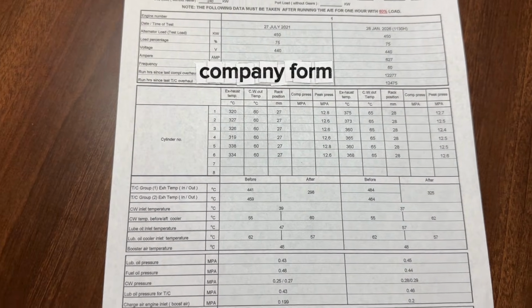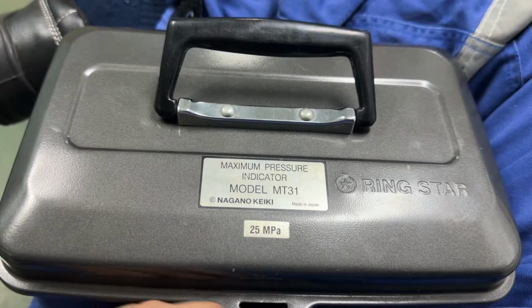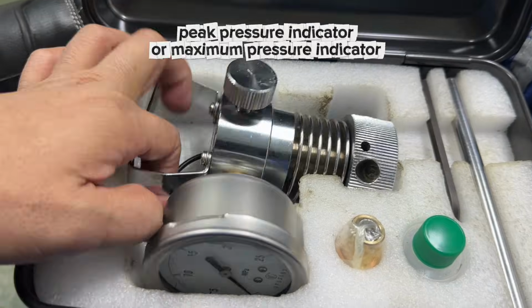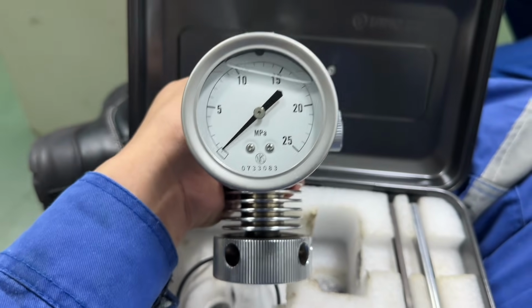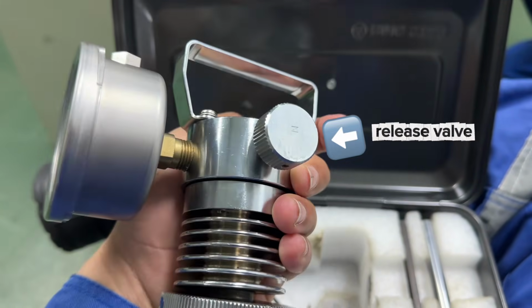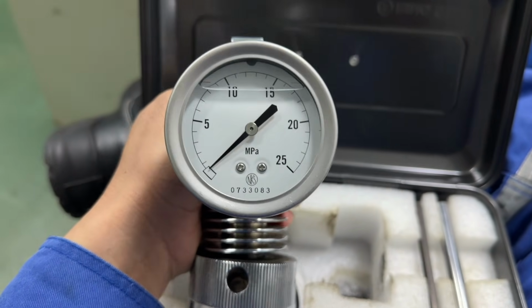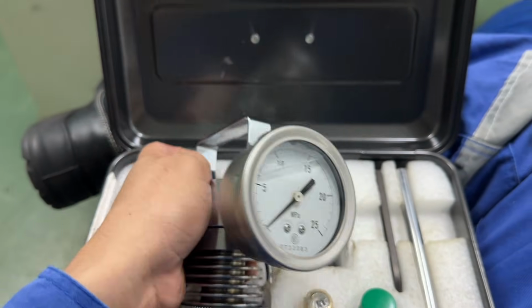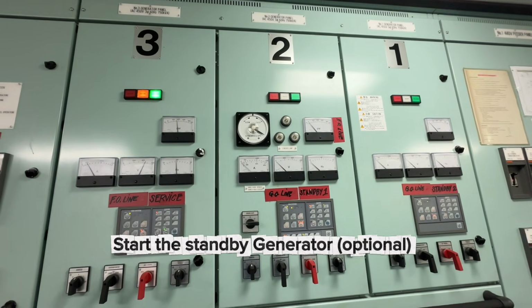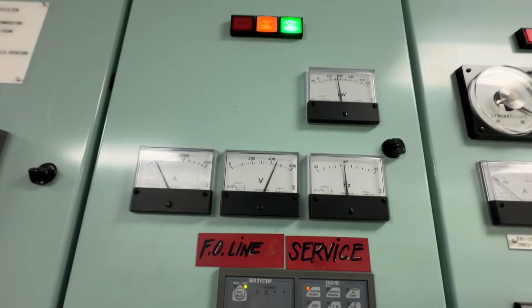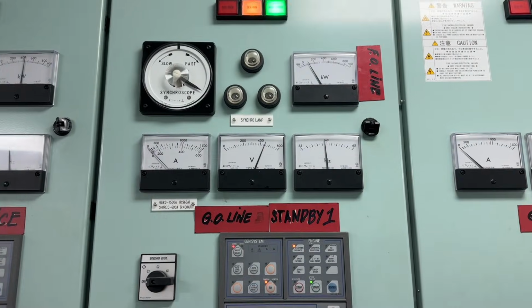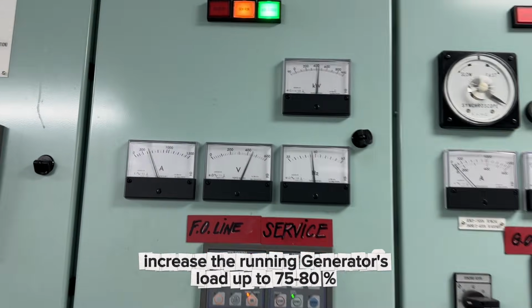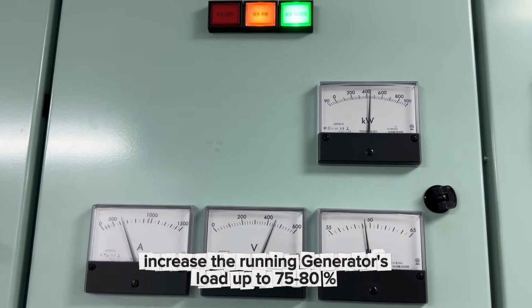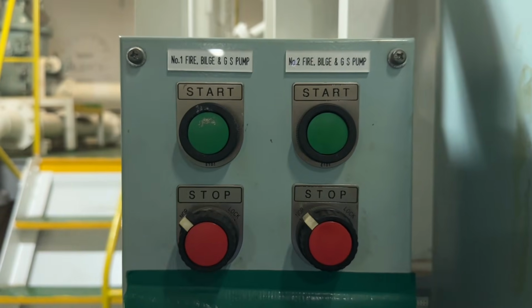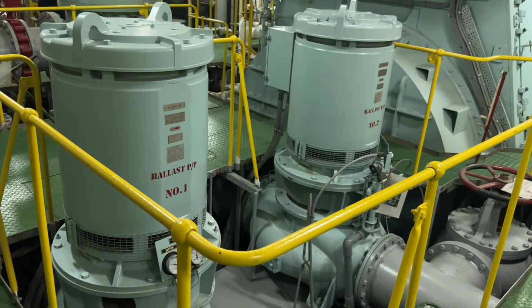Before we start, we need to prepare the company form for the performance report and the peak pressure indicator. Then, start the standby generator. It is optional, and synchronize it with a running generator, the one we're taking the performance test for, for safety purposes. Then, slowly increase the running generator's load up to 75 to 80% by starting some machinery, either the fire and bilge pump, ballast pump, or main air compressor.